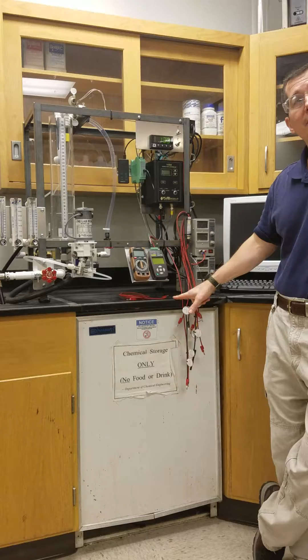And one thing that we're going to standardize in this lab is 4 to 20 milliamp signals. There's a couple of reasons for that. One is that that's kind of the industry standard. When you have electronic equipment, they have different types of outputs. The differential pressure transducer has a 0 to 100 millivolt output that is what's called ratiometric. In other words, its output depends on the supply voltage. So that's a 0 to 100 millivolt output.